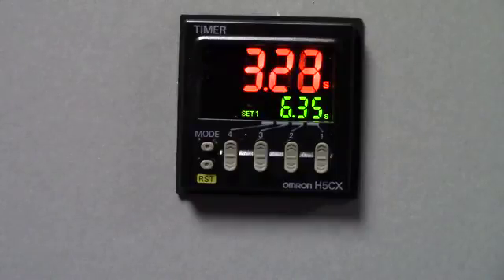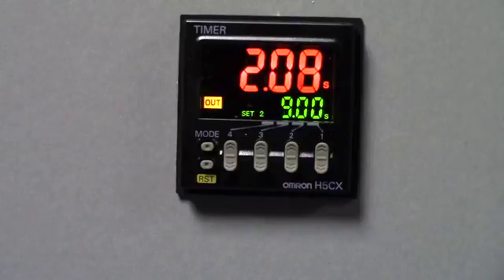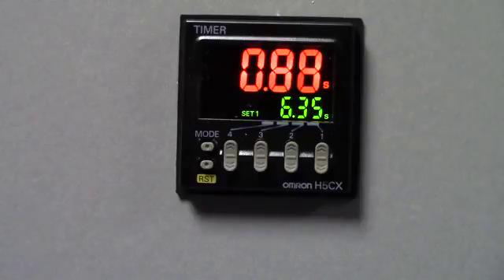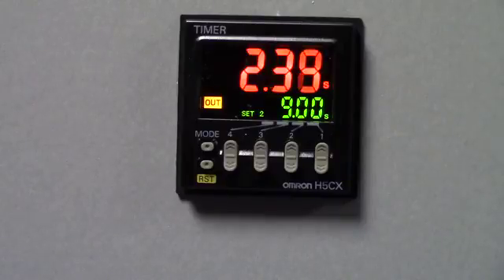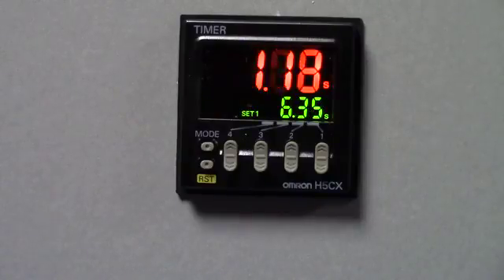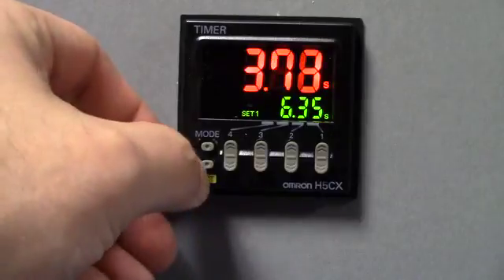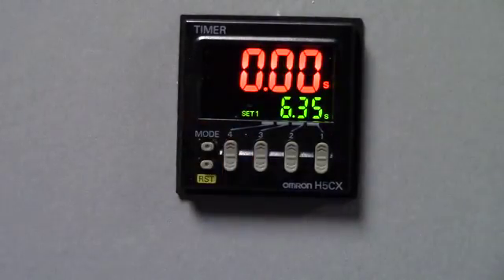So it is in a twin timer mode where we have our on time and off time cycling on and off. As you can see, the output light comes on when it reaches its desired time to indicate that the contacts have transferred. Right now, the contacts are in a normally open state, and as the output light came on, it has now transferred over to a normally closed state. By pressing the reset button, that allows us to bring it back to zero and stop the timing process.